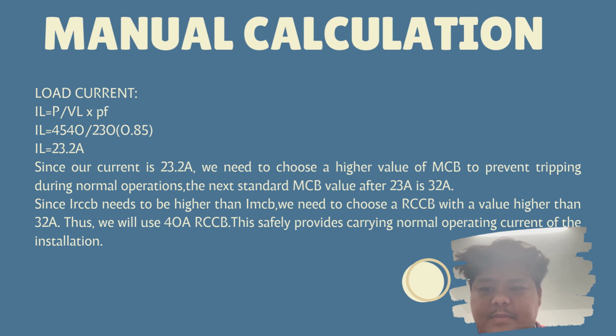And for the IRCCB, it also needs to be higher than the IMCB for safety reasons. So we need to choose an RCCB with a value of over 32 amperes. The next one is 40 amperes for the RCCB. So this safely carries the normal operating load of the installation.